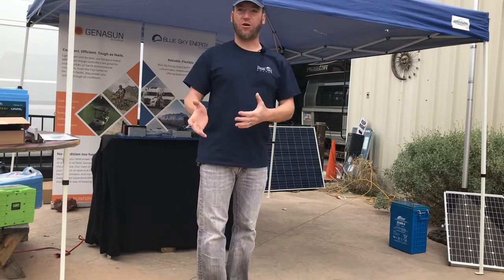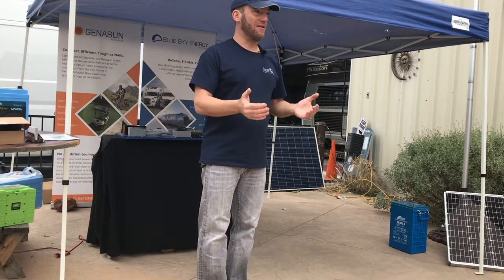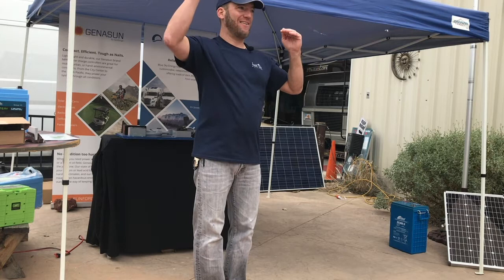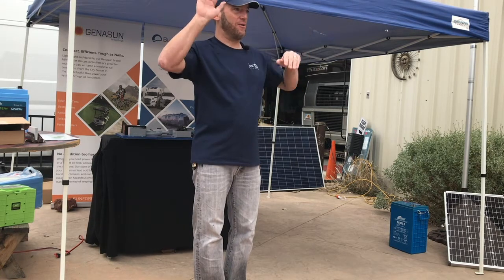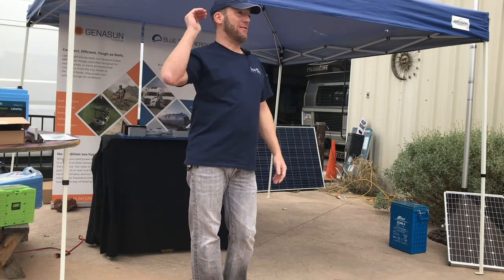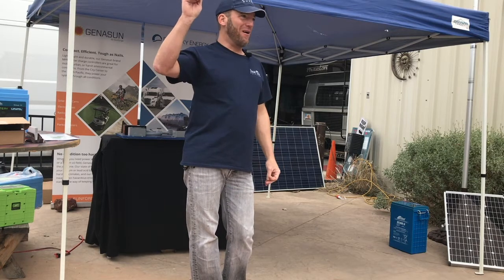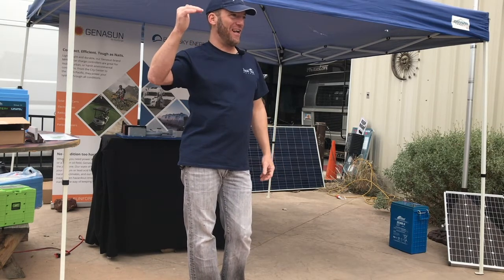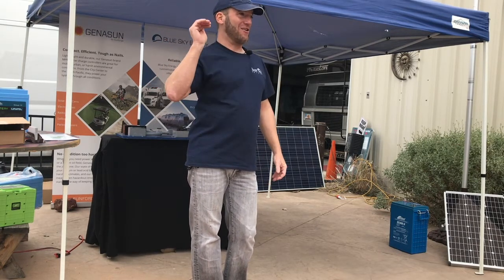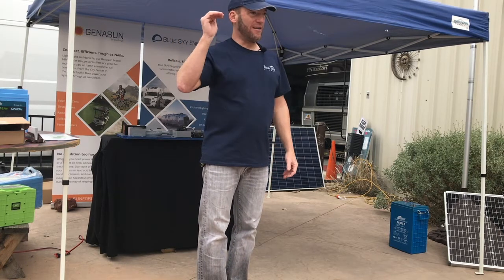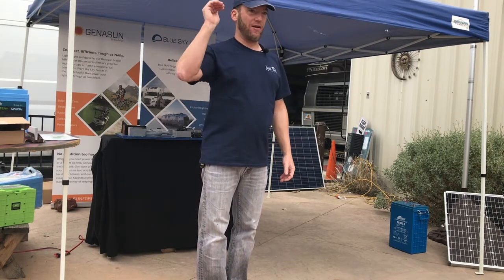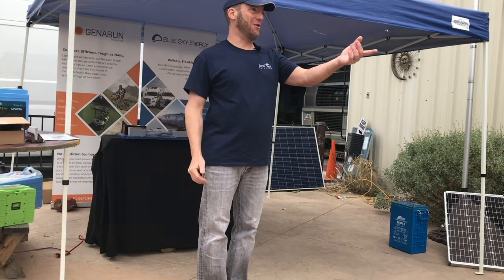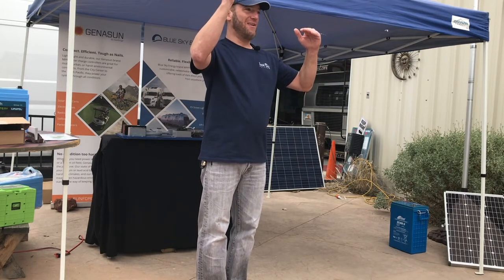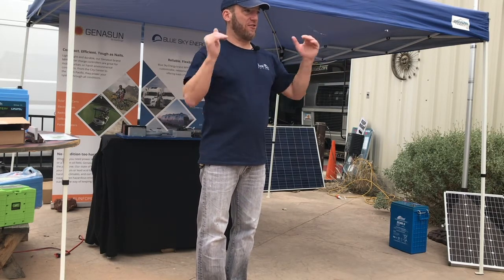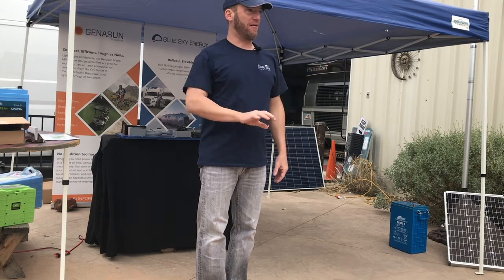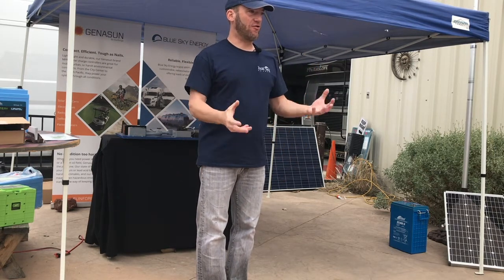Because it's just trying to provide enough current to maintain a voltage, when we say multiple charge sources, the highest voltage wins. Whoever's trying to get the highest becomes the target of that particular controller. You may not have enough juice to get there—if your batteries are heavily sulfated or need more power, it'll still try to reach that set point, reaching for the higher goal. So if your PWM is shooting for one voltage and your MPPT is shooting for another, each controller just stops at the high point it's set to, depending on its charge mode and phase.